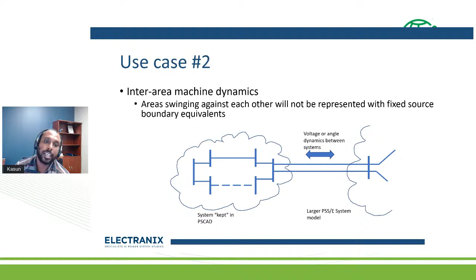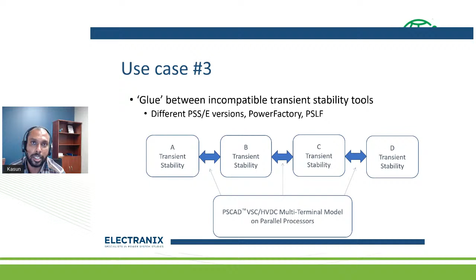Another important part of hybrid simulation, or co-simulation, is model incompatibility. Sometimes the network is modeled in one software while the device or IBR we're analyzing, like a wind farm or PV plant, is modeled in a different software. So what we do is model that particular part, the wind farm or PV, in one software, and the rest of the network in a different software, then connect them together and co-simulate to see the behavior of the IBR. That's one of the main uses when we don't have all the models available in a single tool.